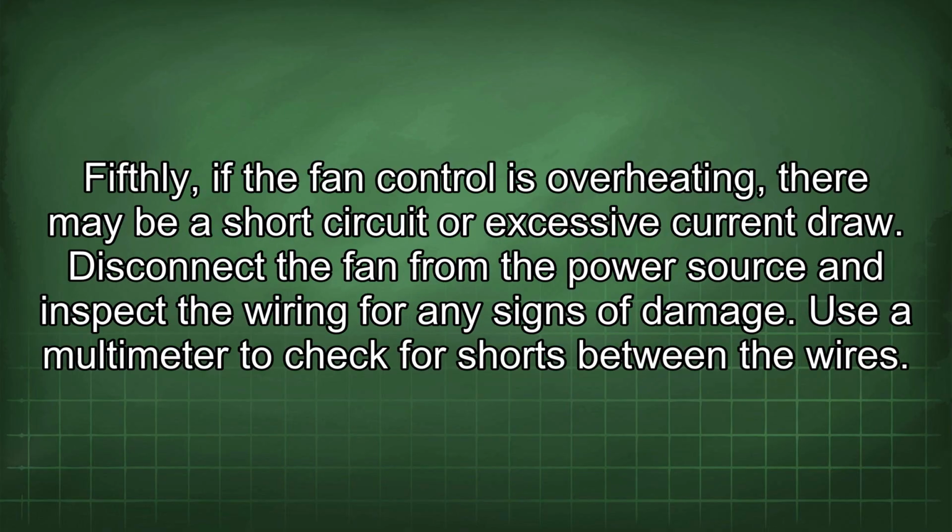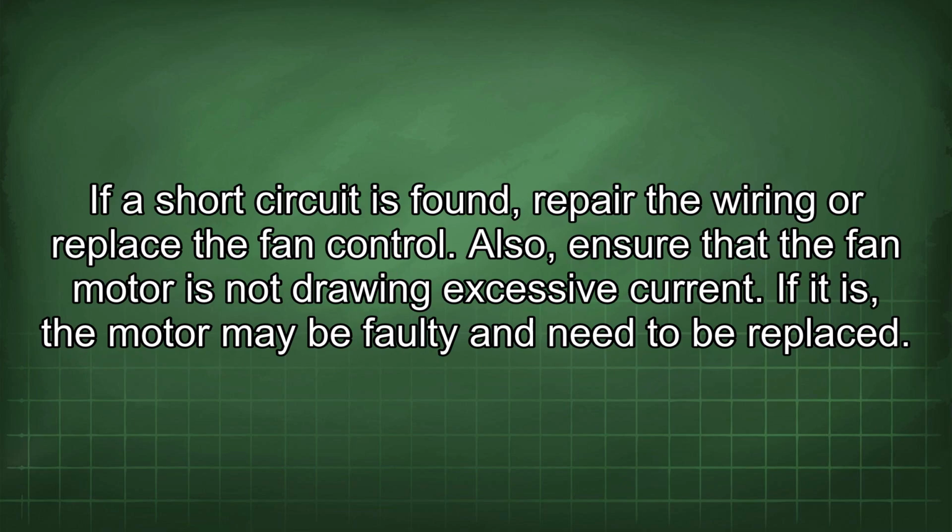Fifthly, if the fan control is overheating, there may be a short circuit or excessive current draw. Disconnect the fan from the power source and inspect the wiring for any signs of damage. Use a multimeter to check for shorts between the wires. If a short circuit is found, repair the wiring or replace the fan control.